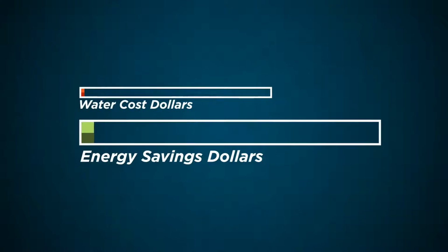Evaporative cooling technologies of today are designed to minimize water use and deal with a range of water supplies with varying quality. The money saved from reduced electricity consumption and peak demand can be used to offset the cost of the water used, which is typically only 3 to 15% of the electricity savings.